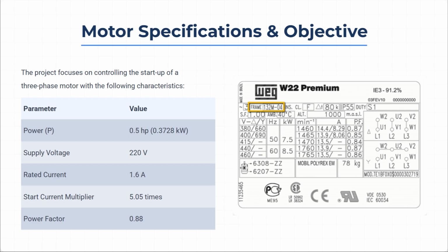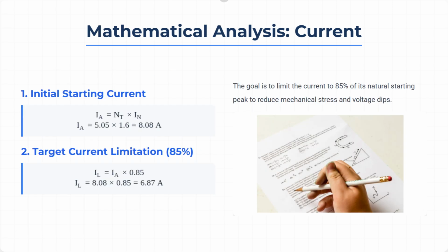The inrush current peak is 5.05 times the nominal current. Our main objective is to limit this current peak to reduce mechanical stress and voltage drops on the line. Analyze target current. First, we calculate the initial inrush current by multiplying the factor by the nominal current, that is 5.05 times 1.6 equals 8.08 amperes. The goal is to limit the current to 85% of its natural starting peak. This gives a limited current of 8.08 times 0.85, that equals 6.87 amperes.